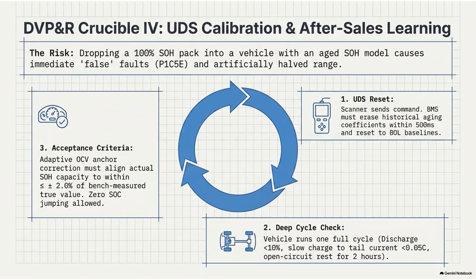But the software validation isn't over. A wiped memory isn't enough. The BMS must prove it can accurately map the new hardware. The test requires the technician to perform one complete deep cycle on the new pack. They discharge the new battery down below 10% SOC and then plug it in for a slow AC charge until the tail current drops to near absolute zero.